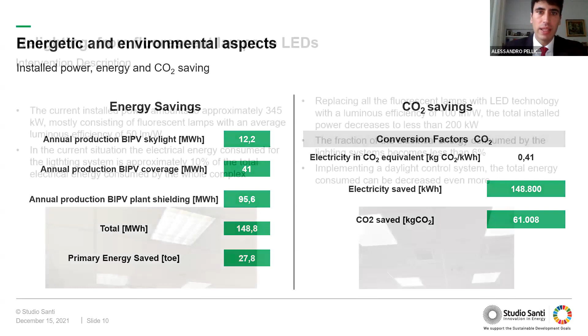The next intervention consists in the relighting of the building. The actual situation consists in fluorescent lamps with an average luminous efficiency of 50 lumen per watt, and a count of almost 345 kilowatts of electric power. In the current situation, the lighting system accounts for almost 10% of the total electrical energy consumption of the whole complex. The LED technology will help us to almost halve the power installed, increasing the efficiency and lowering the fraction of electrical energy to less than 6%.